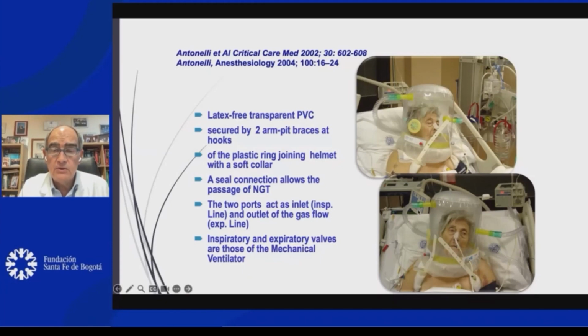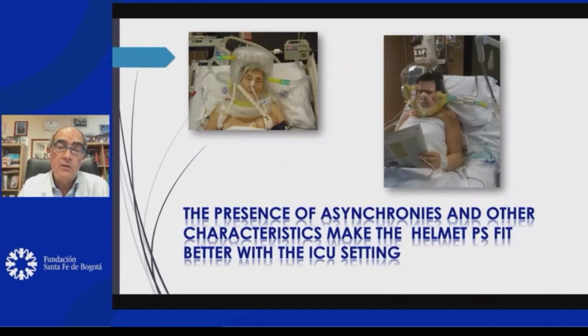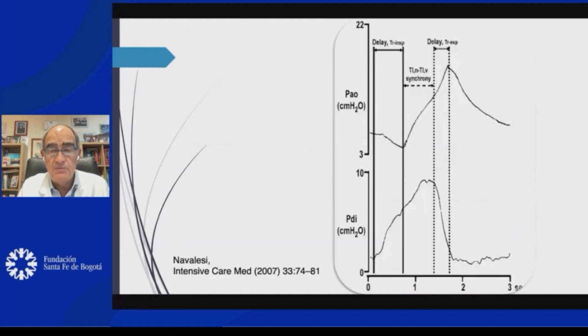And there are two ports for the inlet and the outlet connected to the different lines, inspiratory and expiratory. And the valves are those of the mechanical ventilator. One of the main things that we have to take into consideration is that by using this device, the presence of asynchronies and other characteristics may make the helmet, when it is used as a pressure support modality, fit better with the ICU setting. Notwithstanding the fact, as I already mentioned, that it has been largely used also outside the ICU, even though this use outside the ICU in many different centers was adopted in CPAP modality.